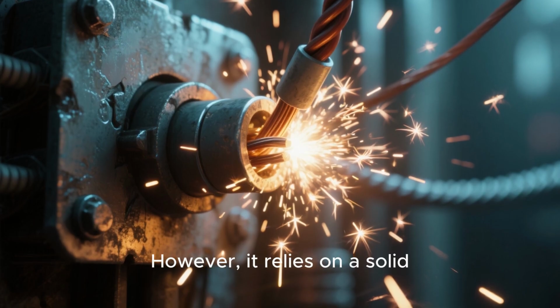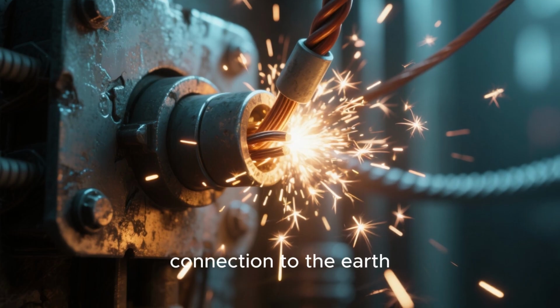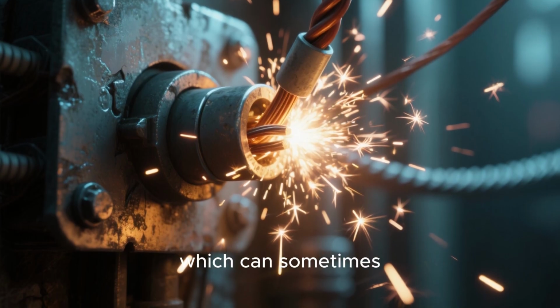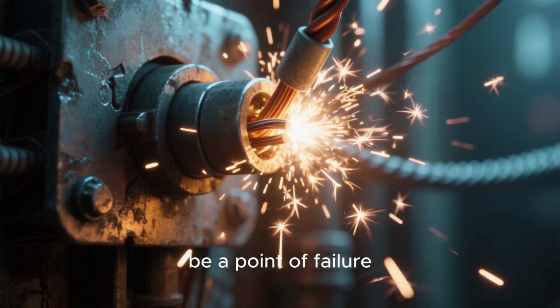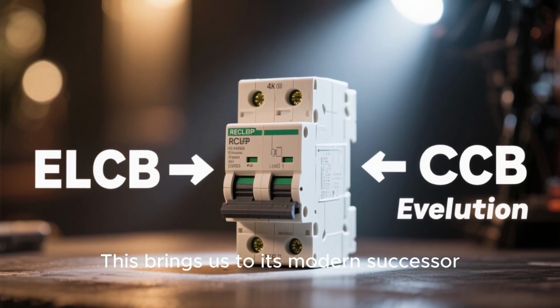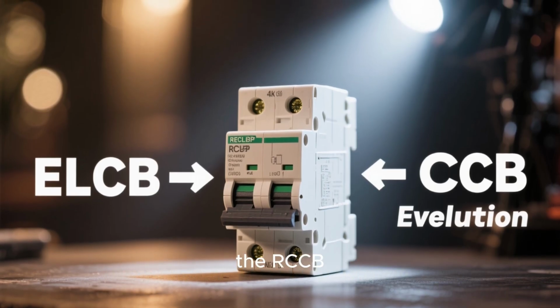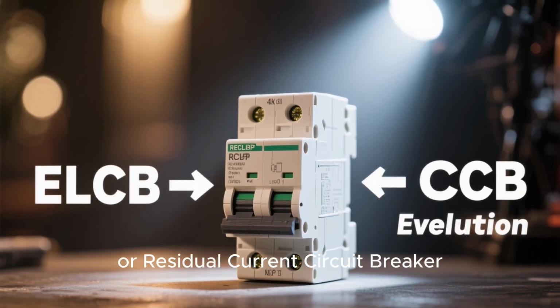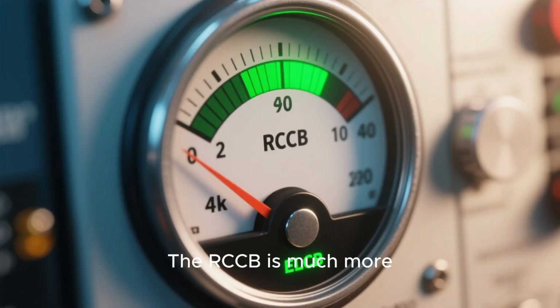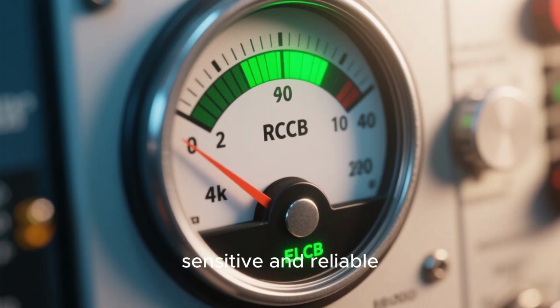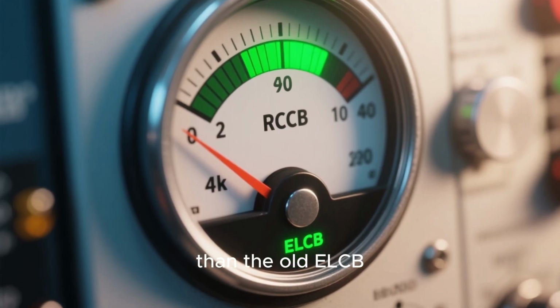However, it relies on a solid connection to the earth wire to work properly, which can sometimes be a point of failure. This brings us to its modern successor, the RCCB, or Residual Current Circuit Breaker. The RCCB is much more sensitive and reliable than the old ELCB.